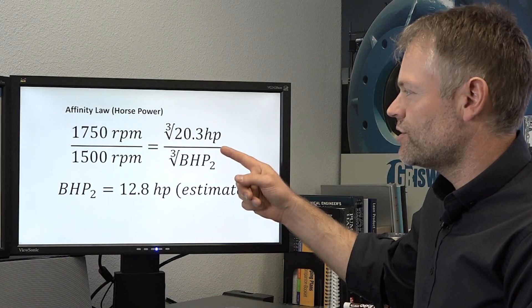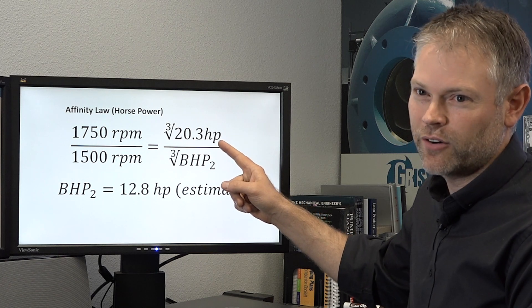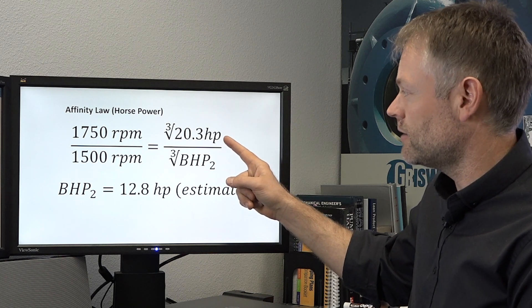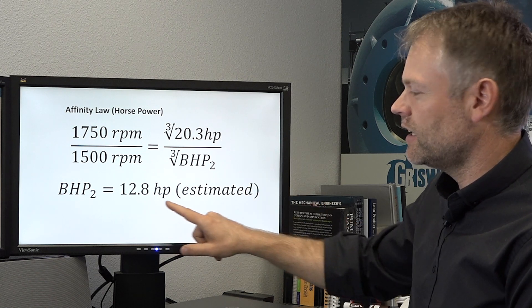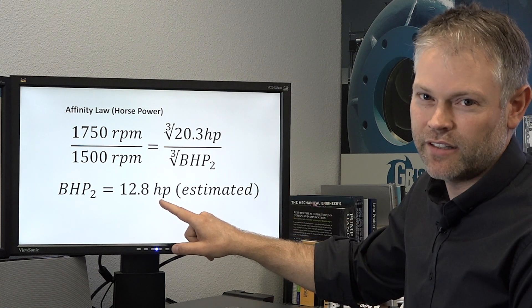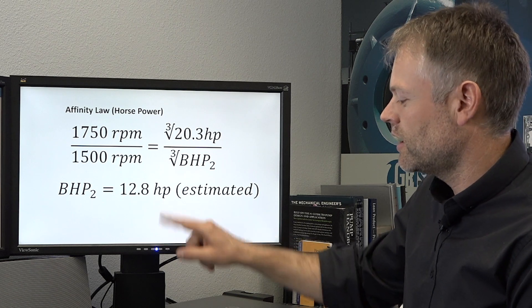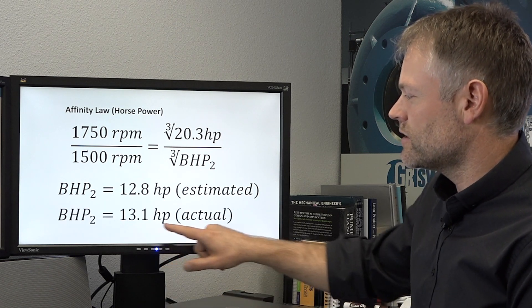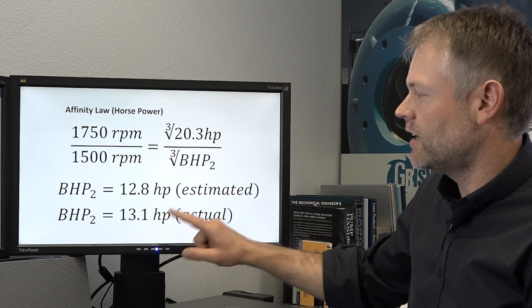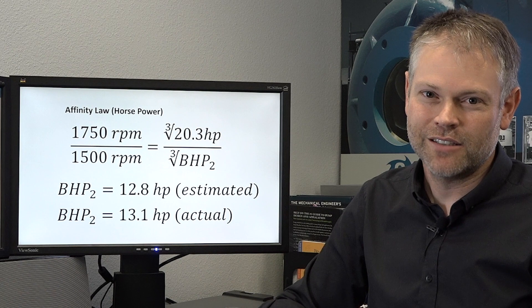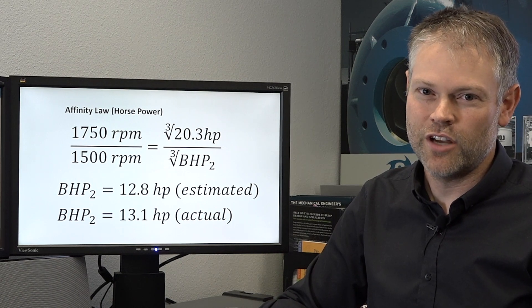Finally, let's look at what happened to the horsepower of the pump as it was operating. We started at 20.3 horsepower. The affinity laws would predict 12.8 horsepower performance, and in the test lab we saw that it was actually performing at 13.1. So again, the affinity laws did a very good job of estimating the performance change.